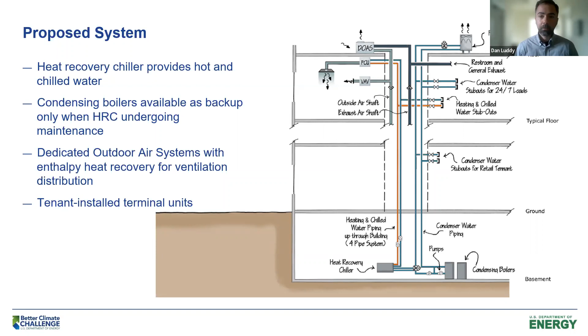In Seattle, it's a cold climate, but it's a relatively mild cold climate. We don't see days below 0 degrees Fahrenheit that often. So we're comfortable designing a system around a heat pump, this particular heat pump that can operate down to those temperatures that we see in a winter condition in Seattle and do so comfortably. In a colder climate, it could also be possible to use those boilers as a backup situation where they could automatically turn on and provide supplemental heating on the coldest of days if the heat pump wasn't able to meet the capacity. So there are hybrid solutions available out there too, where the heat pump is the first stage, covers most of the heating, and then on those particularly cold days, you could have some sort of gas backup. Next slide, please.